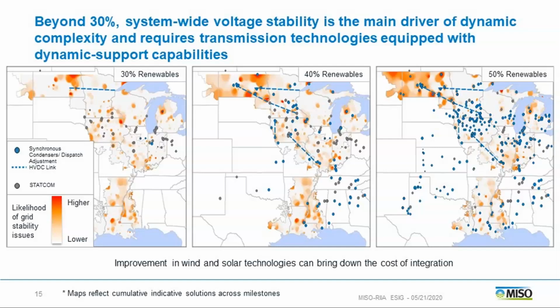Initially, those could be solved with relatively conventional means through STATCOMs and synchronous condensers. But as the penetration increased beyond 30% into 40%, we started to see a need for non-traditional solutions. The amount of traditional solutions needed was too much, and we were seeing too much interaction between them to effectively solve the cases. So we deployed HVDC as the proxy for a solution here, something that could connect the weak areas to the stronger areas of the system.